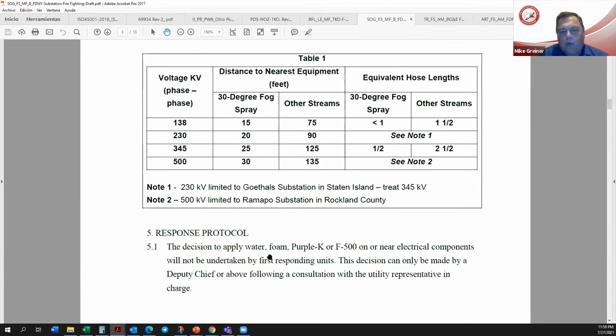Knowing that in the US a hose lay is actually 50 feet, they now use their hose to measure the distance they are from the transformer - either half a hose, or in the case of 125 feet, 2.5 hoses. That's how they mark off the distance in the field to make sure they're standing back far enough to apply the encapsulator agent solution without the leakage current coming back to the nozzle.